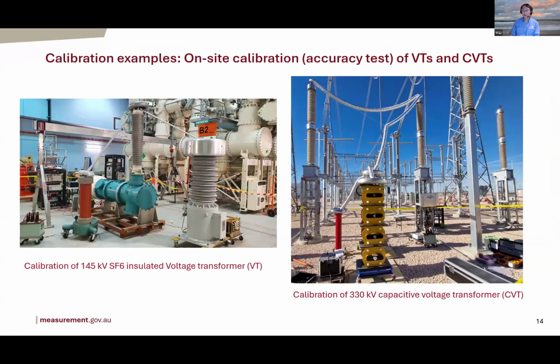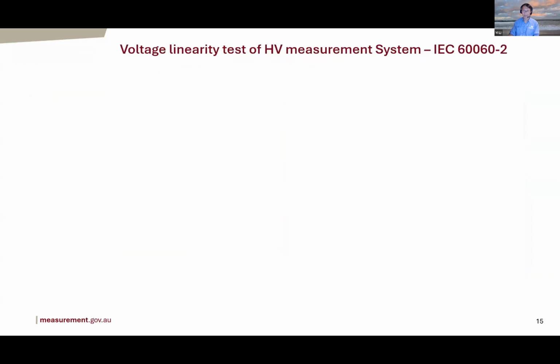This is an example of calibration. This is a calibration of a gas insulated, SF6 insulated voltage transformer. It's also a calibration, an accuracy test, because you test the voltage error and phase shift. Again, use the resonance set with an excitation transformer. Because the load is a few nanofarad, it's still quite big, and the voltage is quite high, and the reference capacitor is at the back. This is the voltage measurement. I won't go into too much detail. Just to give you an idea about the voltage generation, which is important.